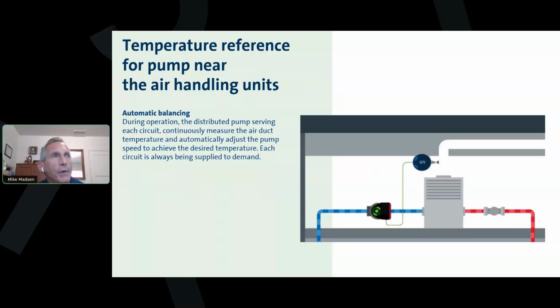Yeah. Well, I think we would probably recommend looking at their pumps to see, with 15-year-old pumps, maybe there is better technology out there. So I think we could make a case on a 15-year-old pump system to upgrade the pumps, replace the control valves with something like this. And then we just need to pencil it out. I'm just going to guesstimate, it's probably going to be in that 5-year range. Well, 5 years, good. For 10 cents a kilowatt hour, that's what I said, right? Yeah, that's really good. It just depends on, do they need anything?